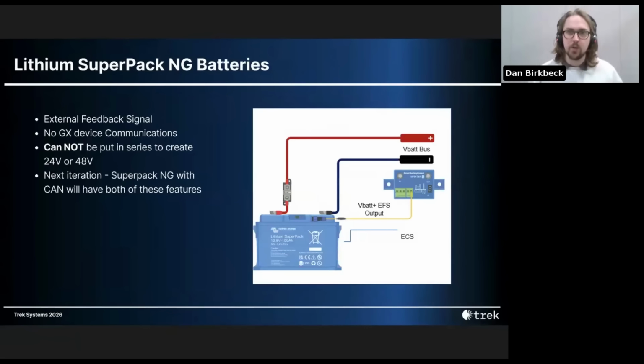Another new feature is the external feedback signal, or EFS. The SuperPack NG includes an M12 single-pole connector that outputs a simple on-off signal. The EFS functions similarly to the ATD, ATC, or allow to discharge, allow to charge outputs on Victron BMS units. It can be used to energize an external relay, trigger a visual or audible alarm, or control devices with remote on-off inputs such as a Battery Protect, solar charger, or Orion XS.